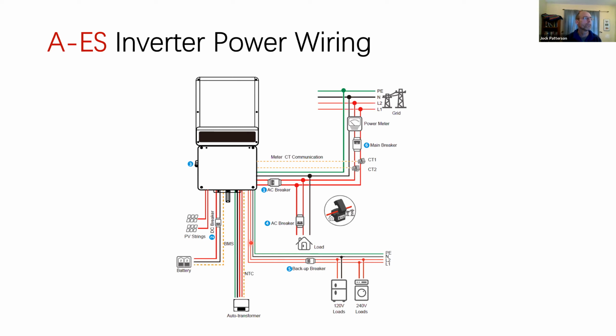The next thing over, and go ahead and interrupt me if I'm not answering your questions, is the essential loads diagram where we have an example of 120 and 240 volt, right? Because you can still do 240 volt backup loads. You always want to consider, though, the startup amperage. It might be locked rotor amps or something, so you always have to consider what you're connecting to the essential loads. But remember, we do have a pretty high output.